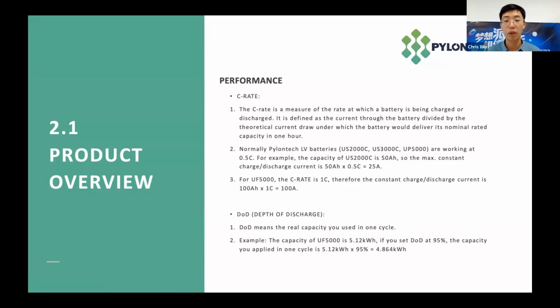For example, the capacity of the US 2000C is 50 ampere-hours, so the max constant discharge current will be 25 amperes. But for the UF 5000, the C rate is 1C, so the continuous charge and discharge current will be 100 ampere-hours multiplied by 1C, which equals 100 amperes. The second point is DOD, which means depth of discharge. This is the real capacity you can use in one cycle. For example, the capacity of the UF 5000 is 5.12 kilowatt-hours. If you set the depth of discharge at 95%, the usable capacity will be 4.864 kilowatt-hours.